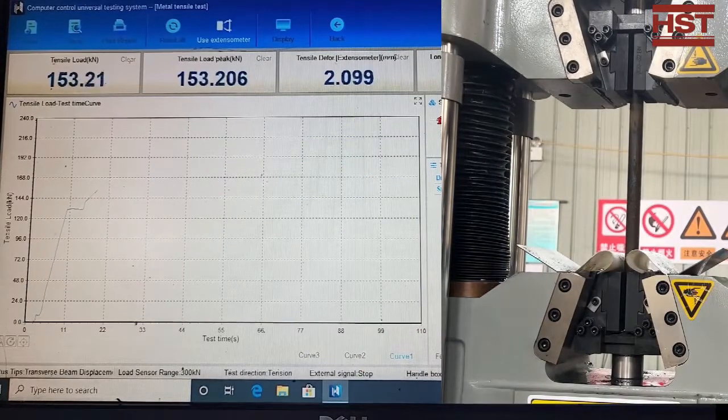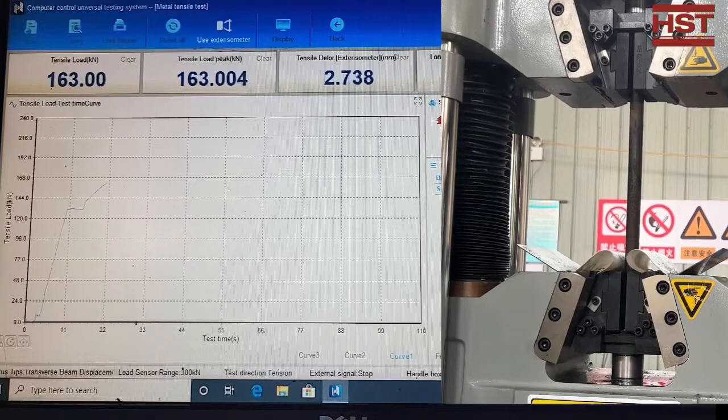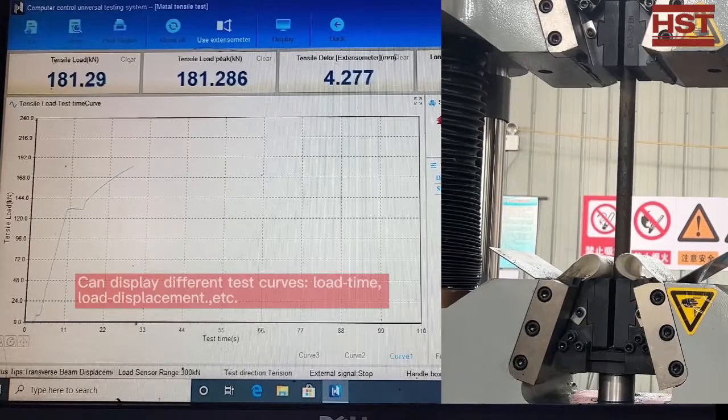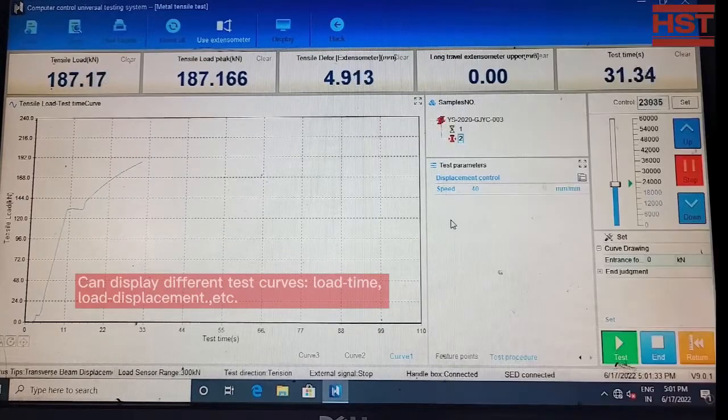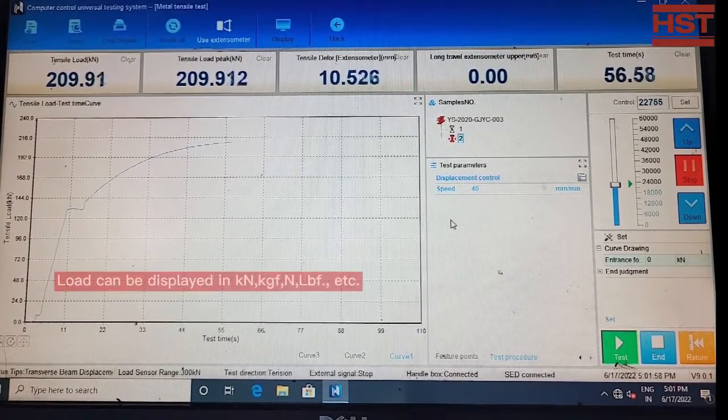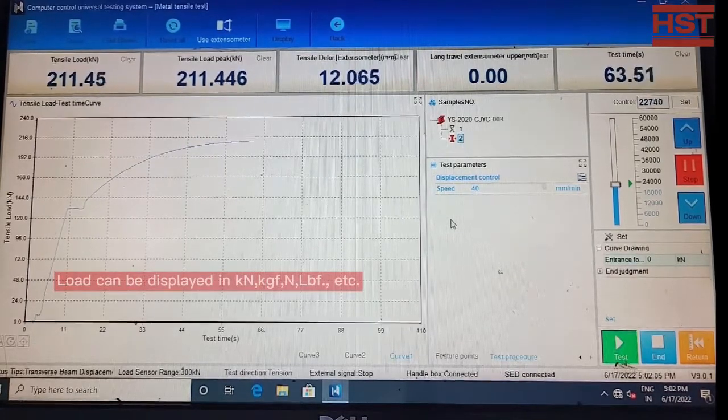The software can display real-time stress-to-strain, force-to-elongation, force-to-time, force-to-displacement, and all other curves. Load can be displayed in kilonewton, pound-force, or kilogram-force as selected by the operator.